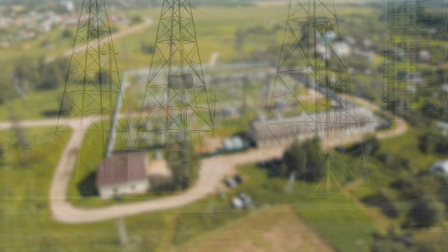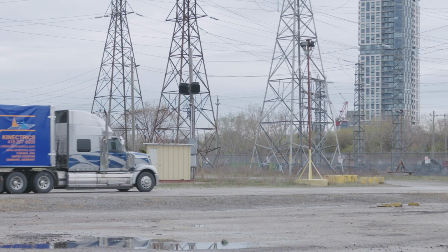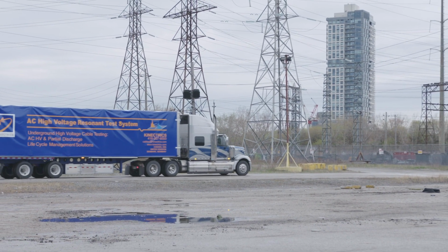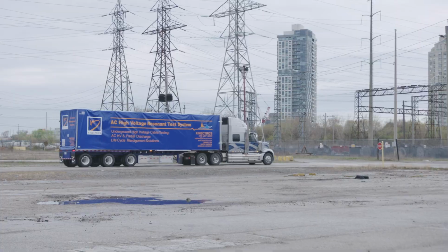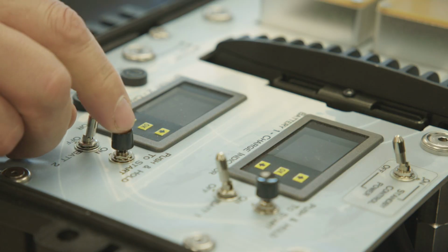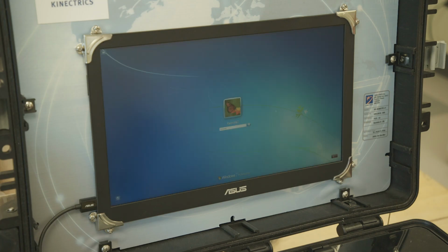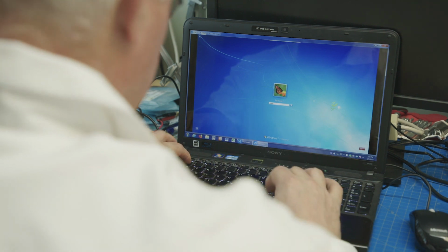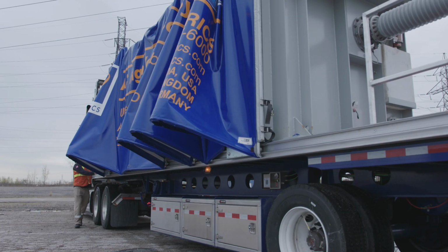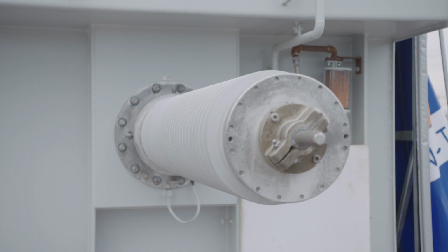Kinectrics has 6 resonant test sets. We have them positioned globally, and that services is mainly withstand test up to 500 kV. And we also do partial discharge localization and diagnostics, whether that's commissioning or maintenance tests for the utilities, the cable manufacturers, or the installers.